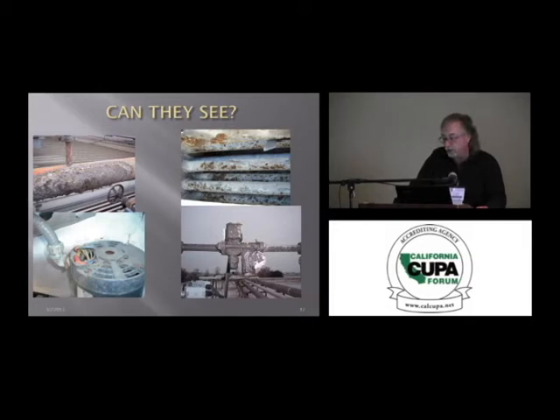A condenser can be totally destroyed in a matter of a few years, when we should get 25 to 40 years out of a condenser, depending on our water quality, how well we do the chemical treatment, and how well we perform our maintenance. But we are finding a lot of that. So make sure that your end users are passivating their condensers and then looking at them from month to month, because that passivation layer can wear out over time. And they'll have to treat it with something like molybdate or another protective coating that's applied in the chemical treatment.